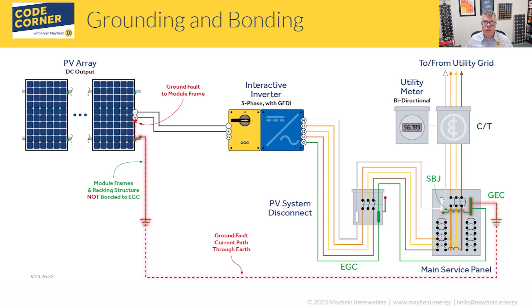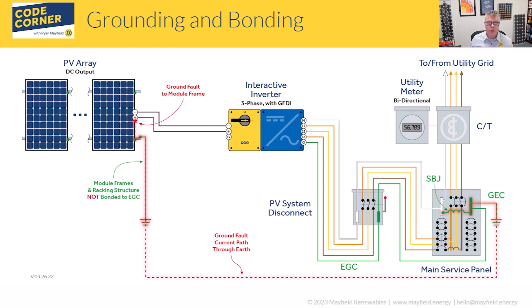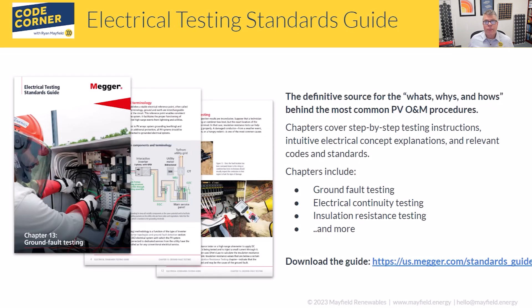This is a key high-level distinction: yes, the racking system may be grounded — it's in contact with the earth — but it is not bonded back to all of the other equipment. That bonding back to the equipment is what's really critical, and it's something that comes up often when talking with people about grounding versus bonding.